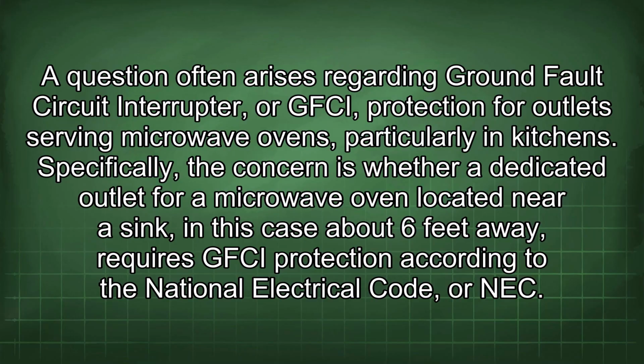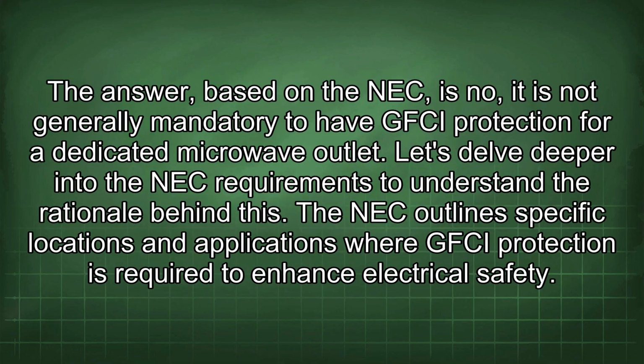A question often arises regarding ground fault circuit interrupter, or GFCI, protection for outlets serving microwave ovens, particularly in kitchens. Specifically, the concern is whether a dedicated outlet for a microwave oven located near a sink, in this case about 6 feet away, requires GFCI protection according to the National Electrical Code, or NEC. The answer, based on the NEC, is no. It is not generally mandatory to have GFCI protection for a dedicated microwave outlet. Let's delve deeper into the NEC requirements to understand the rationale behind this.